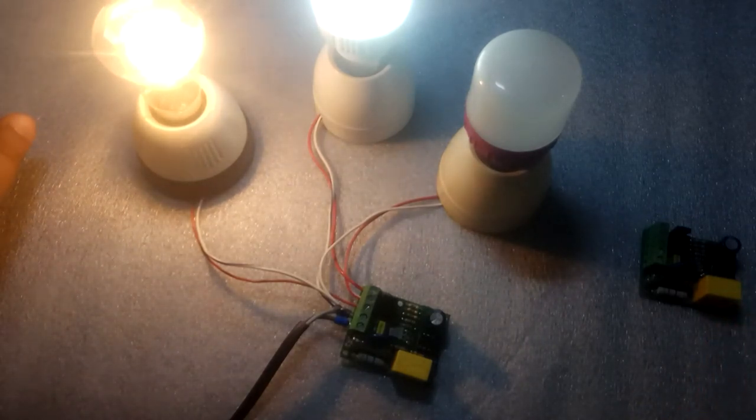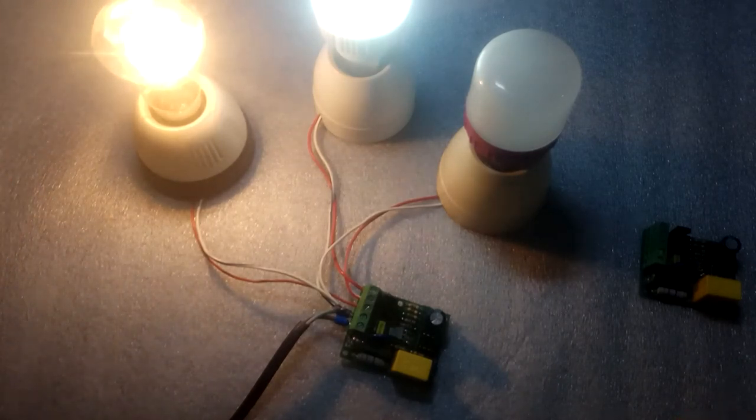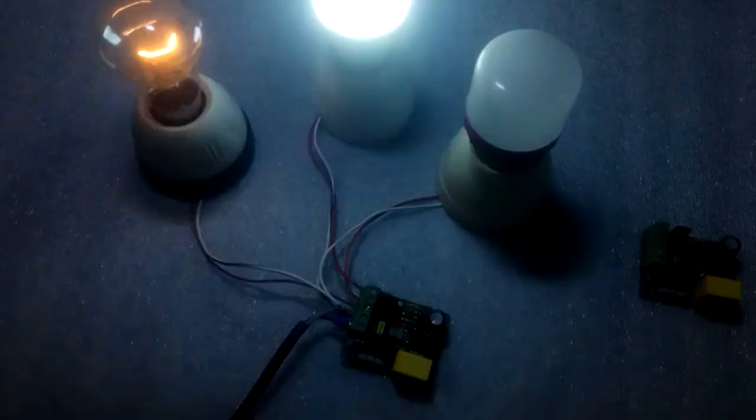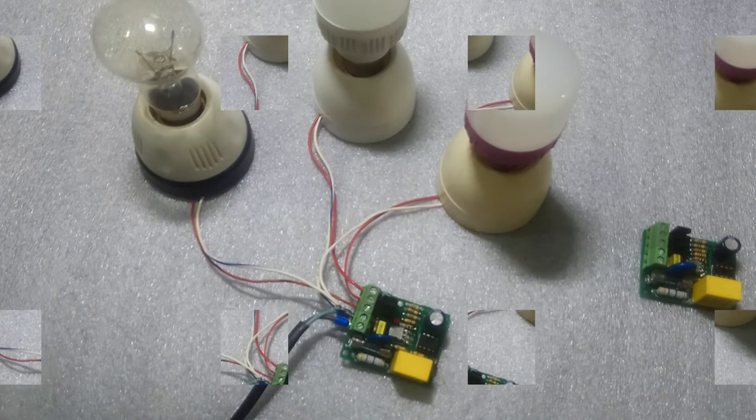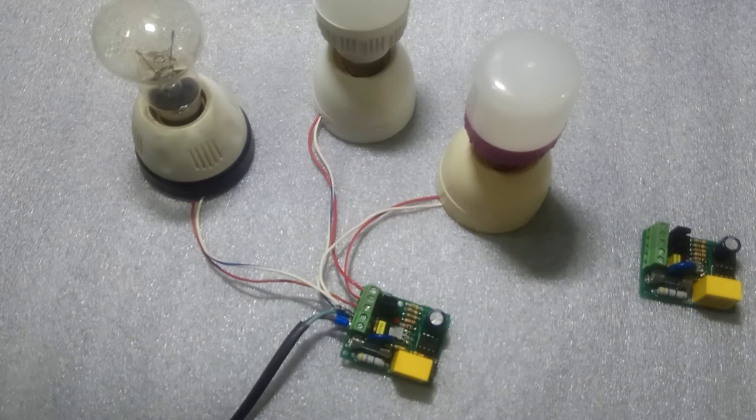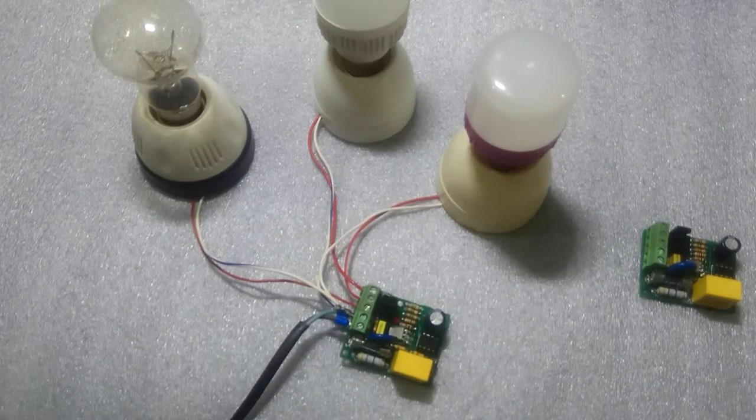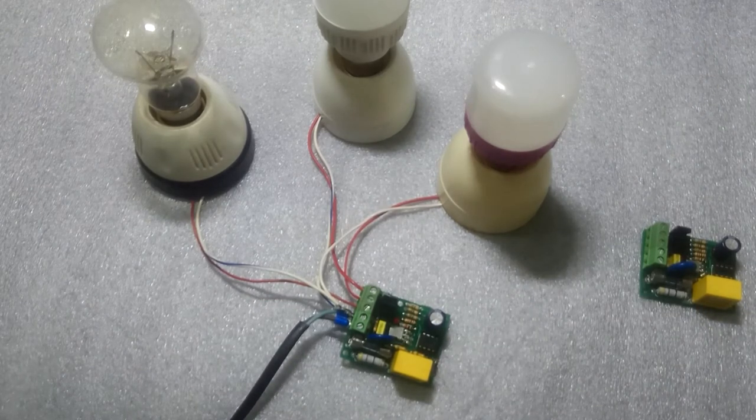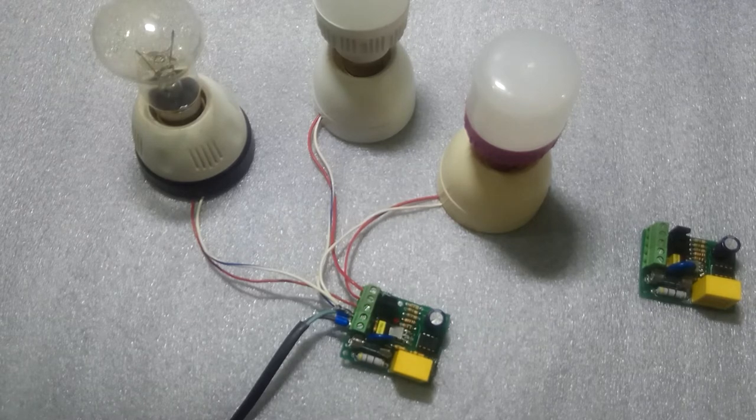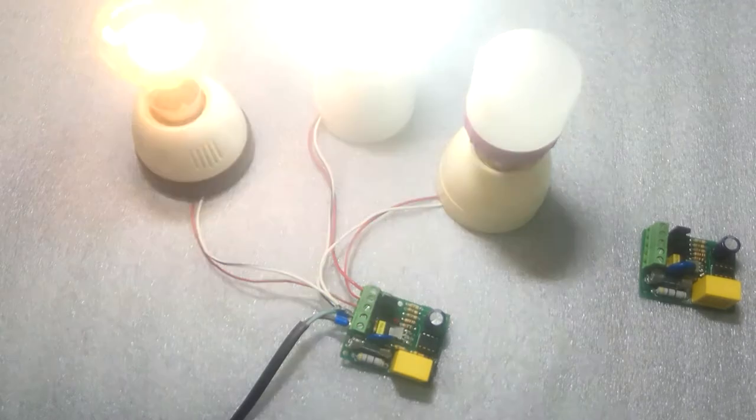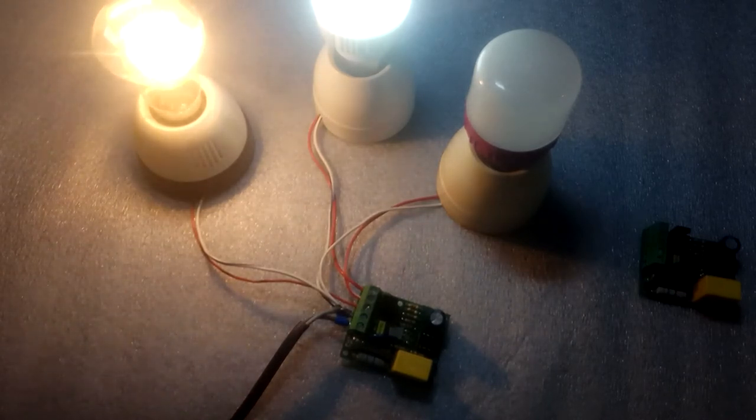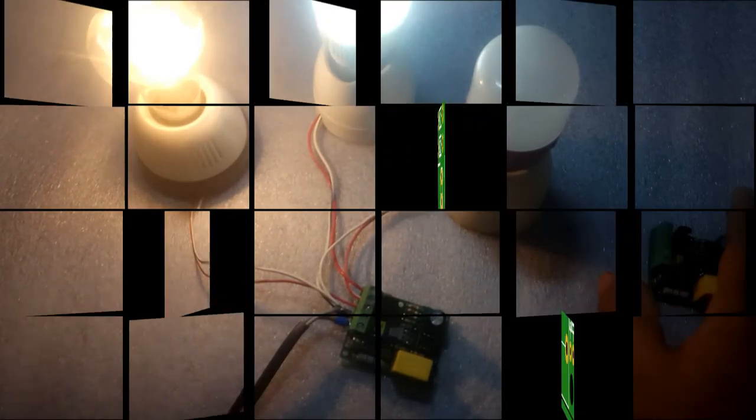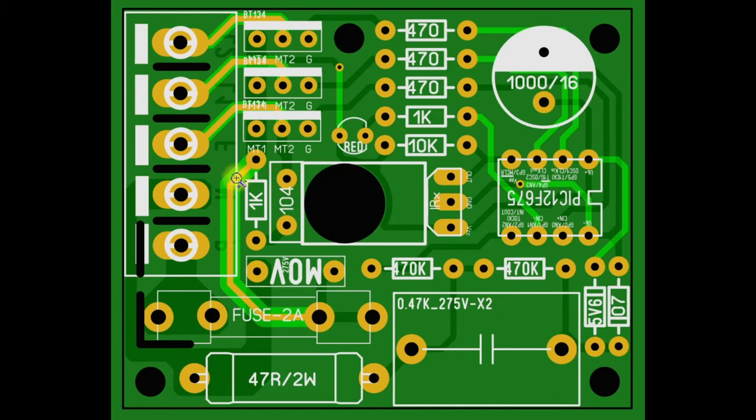...due to load sharing or anything else, let's check. I have already waited two minutes. Now turning the power on... yes, the previous memory is restored. So this demonstrates the memory function.